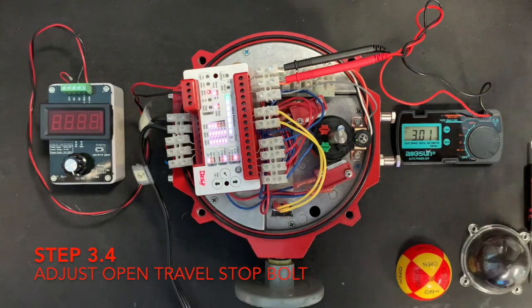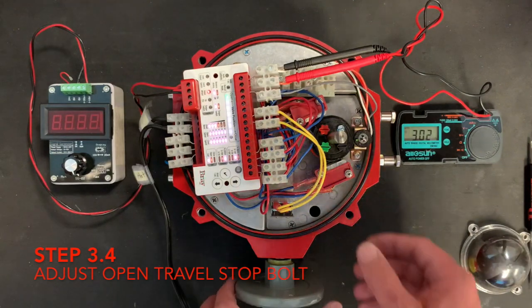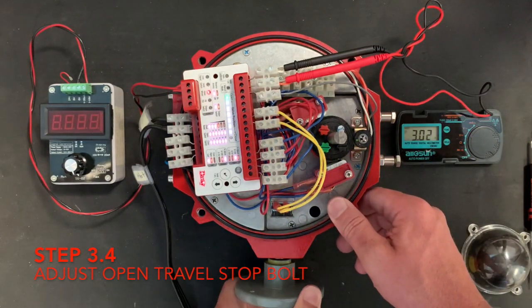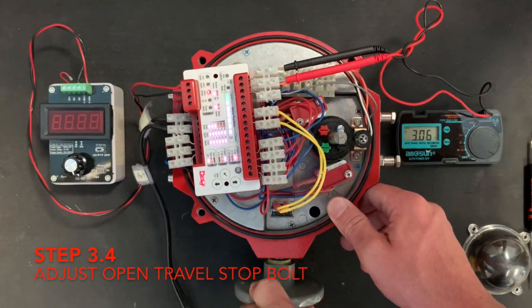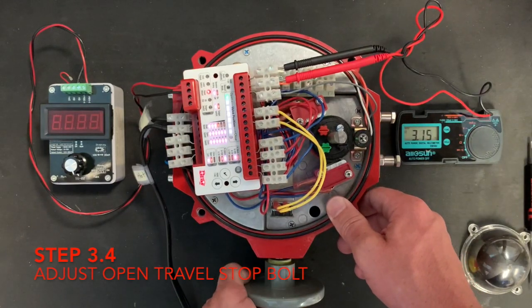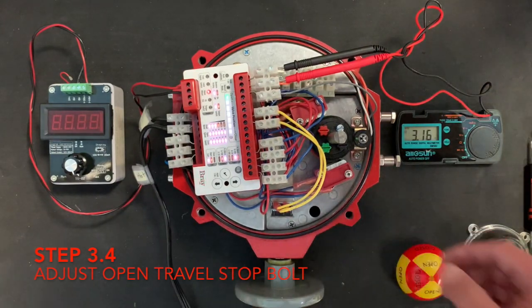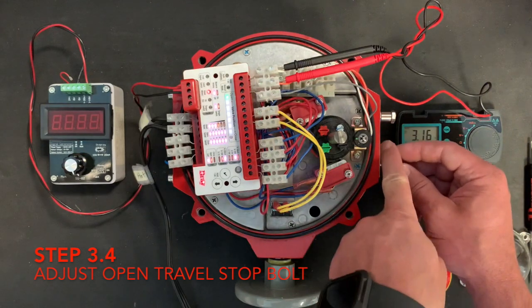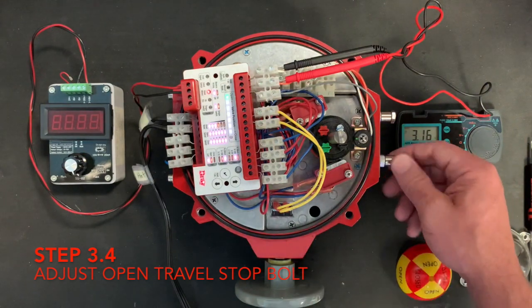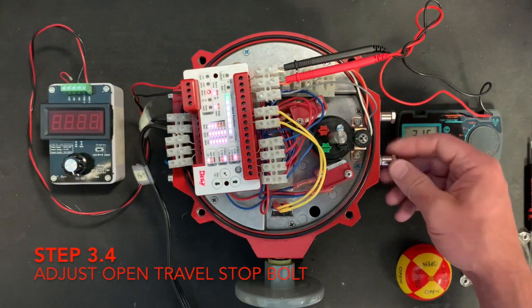With the travel switch in the open position, rotate the hand wheel counterclockwise the number of turns listed in step 2.3. Adjust the open travel stop bolt until it bottoms against the internal segment gear and lock it in position with the lock nut.